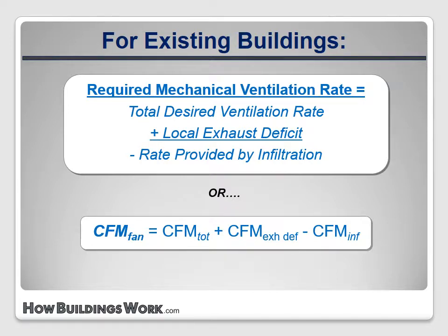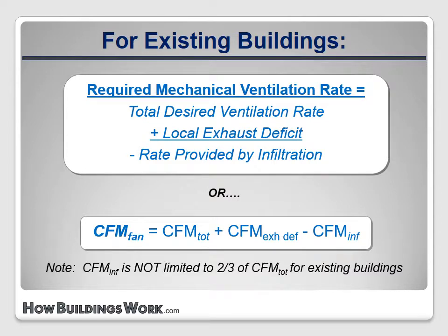Another important change is that the infiltration credit is not limited to two-thirds of the total desired ventilation rate for existing buildings the way it is for new buildings. So if the house is very leaky, no fan will be required.